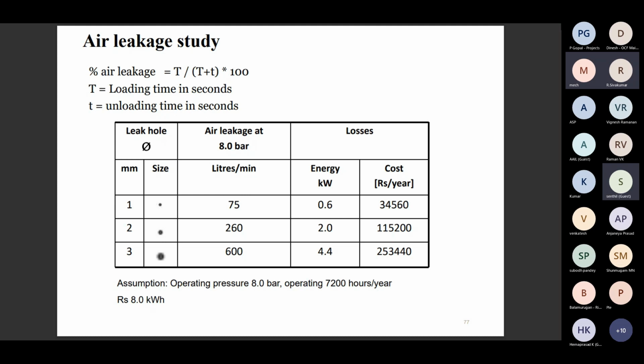Normally, in a very good system without leakage, once the compressor is loaded and the air receiver is filled, there is no air consumption inside the plant. Loading should not happen, the motor should be off, and the compressor should be idle. Practically, in many places there are leakages. Air leaks from the holes and leakage points, so the pressure reduces, and again the compressor loads and goes to unloading. Unloading is more important. The compressor should be unloaded and off. If more loading is happening, that means your plant has more leakages. This is one indicator.